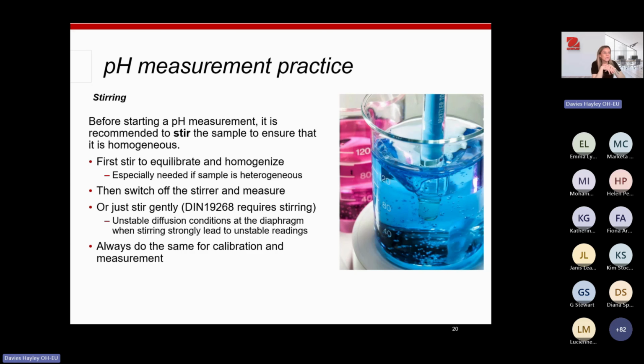Good measurement practice when you're taking the sample is making sure that the sample is the right consistency. So it's always important before you do your pH testing to stir the sample to make sure that it's all homogenized. Then once you've stirred the sample and it's all homogenized and mixed up, you can then switch off the stirrer and then you can measure. If your method requires DIN 19268, which does state that it needs stirring, then it's recommended you stir it gently.